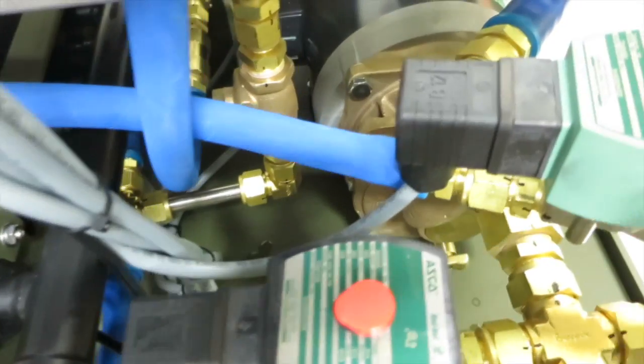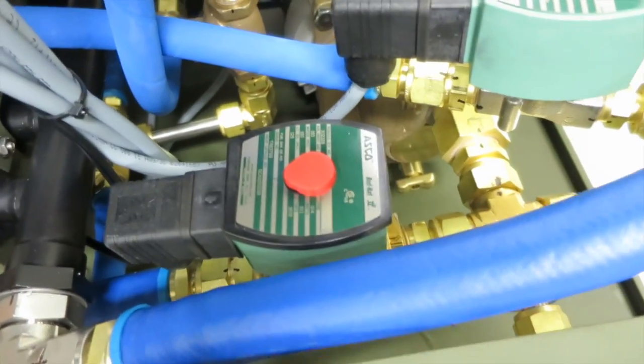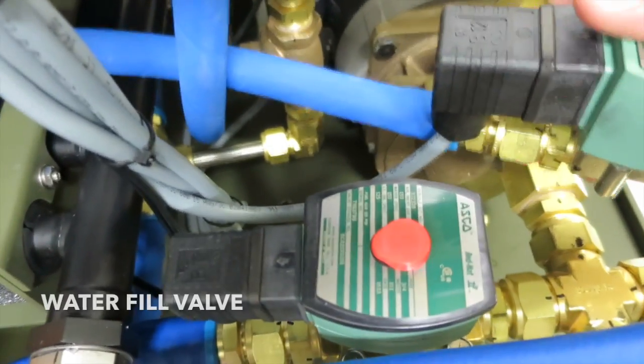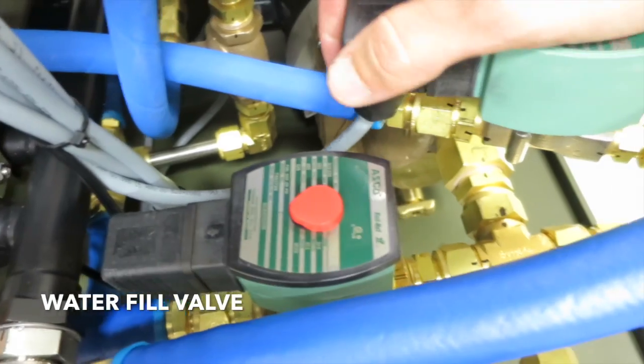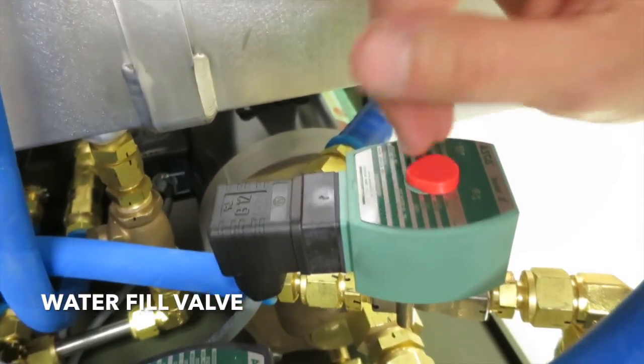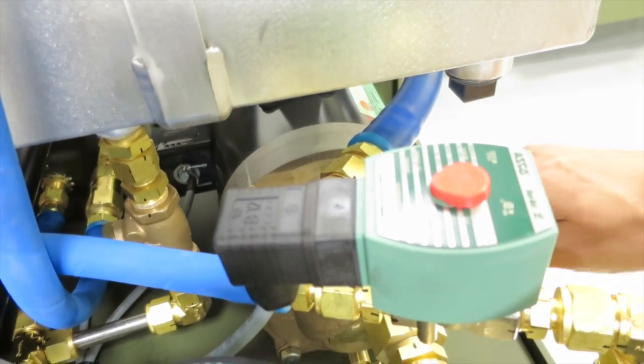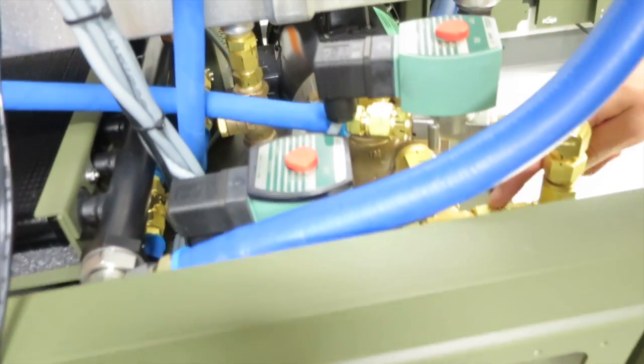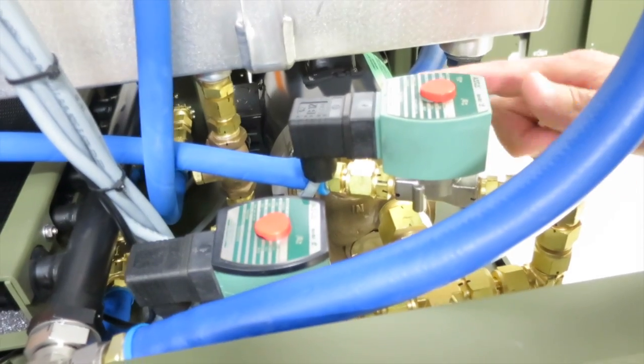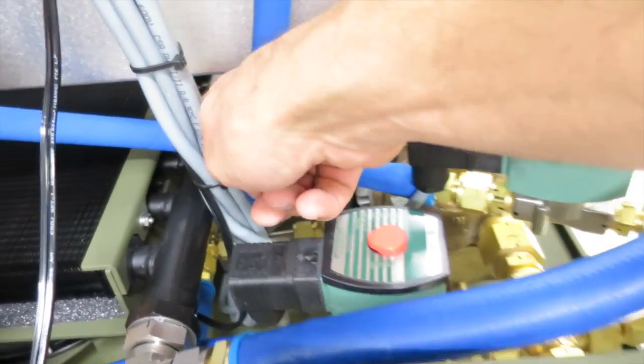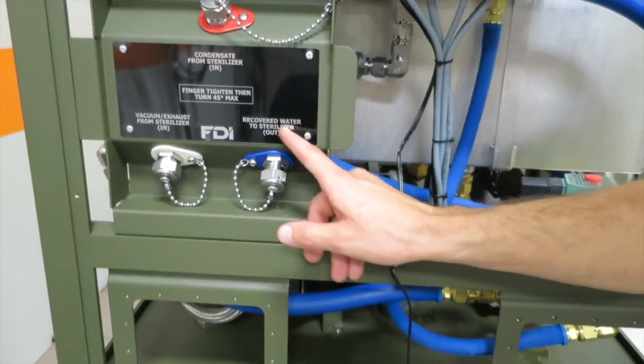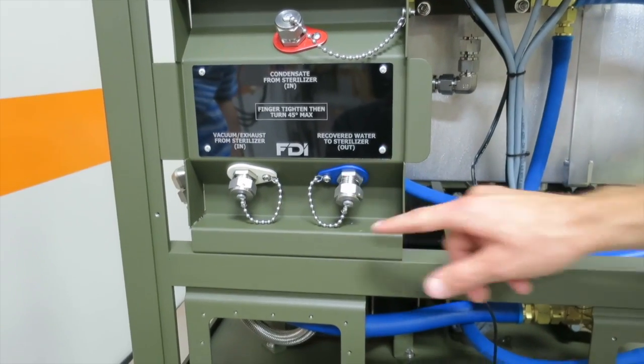Next, we got 2 valves. So we have the water fill valve right here. Anytime you press the toggle switch on the other side of the water recovery system, this valve opens and allows water to come through, out the pump, through the valve, along this hose, and then out right here, recovered water to sterilizer out, the blue hose.